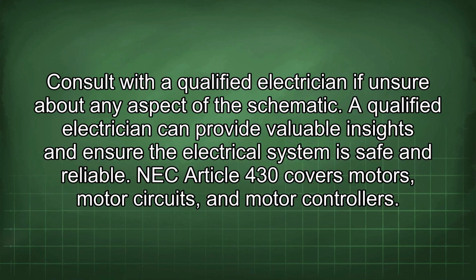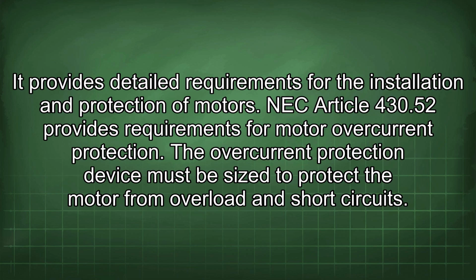NEC Article 430 covers motors, motor circuits, and motor controllers. It provides detailed requirements for the installation and protection of motors. NEC Article 430.52 provides requirements for motor overcurrent protection. The overcurrent protection device must be sized to protect the motor from overload and short circuits.